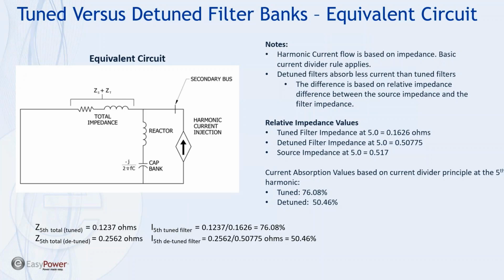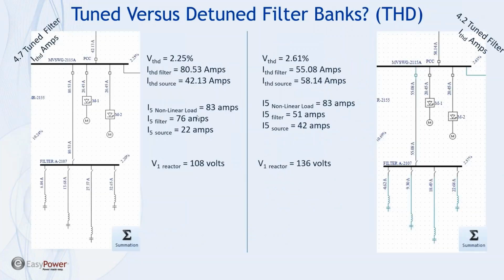So there's a notion out there that if it's a detuned filter, I don't need to do a study. That's totally a false statement. There's also a notion out there that if it's a detuned filter, I don't need to worry about it overloading. And as we noted here, you do have to worry about it overloading. So these are misconceptions. I call it a myth, and it's something that should be avoided. That common notion that a detuned filter does not need any kind of analysis. So I do a couple more plots here. On the left here we have a 4.7 tuned filter.